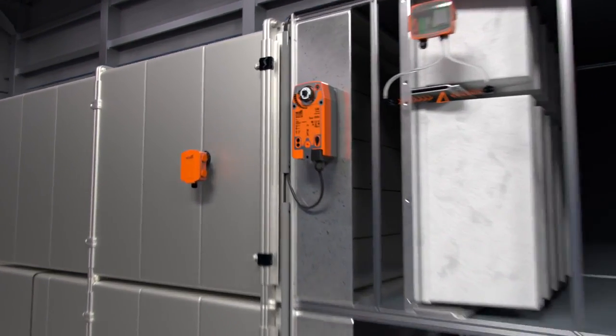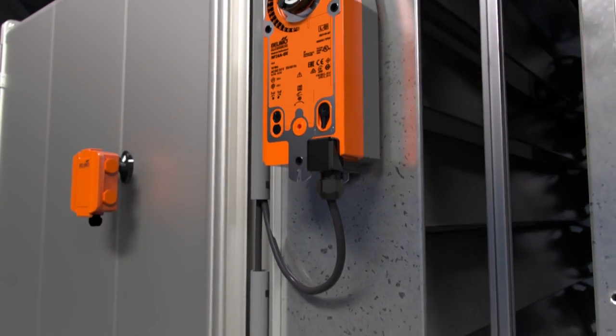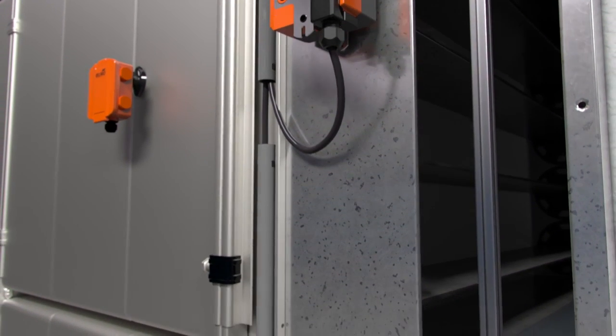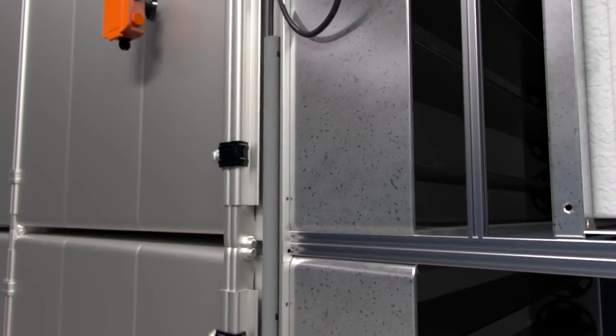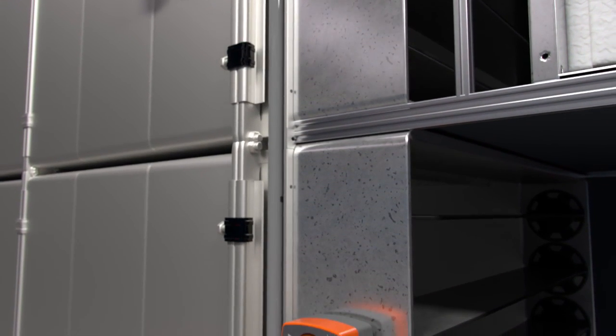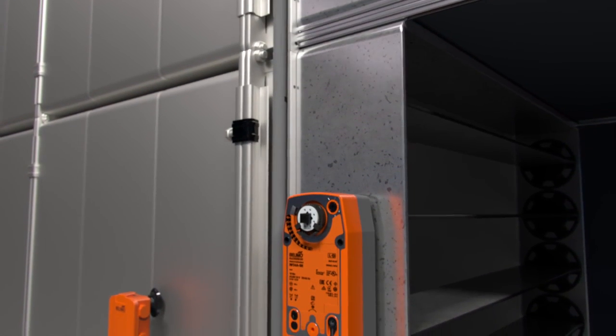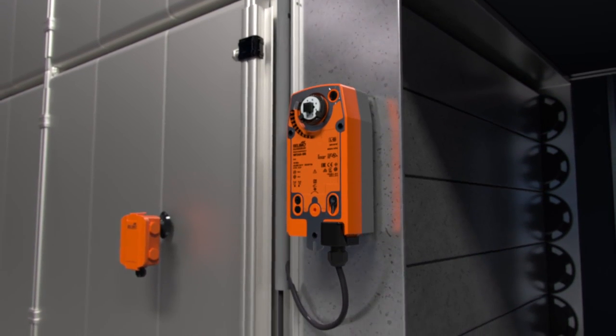A modern air handling unit controls the airflow and the temperature as well as the humidity in an energetically optimized way. In addition, certain start and stop sequences as well as safety states can be handled. To make this possible, various field devices such as actuators, valves and sensors are required. Actuators are required to control the outdoor air and exhaust air dampers. In many cases, fail-safe actuators are used so that in the event of a malfunction, the supply of fresh air can be safely cut off, even without power supply.